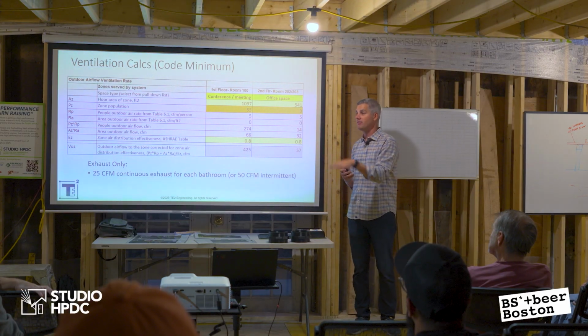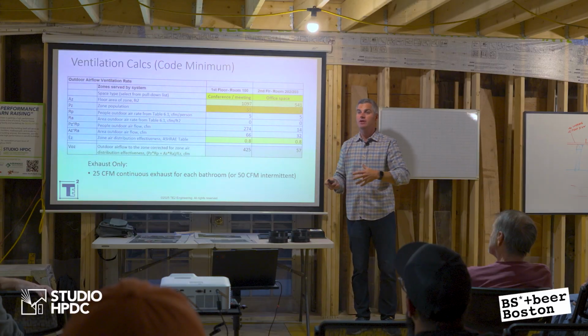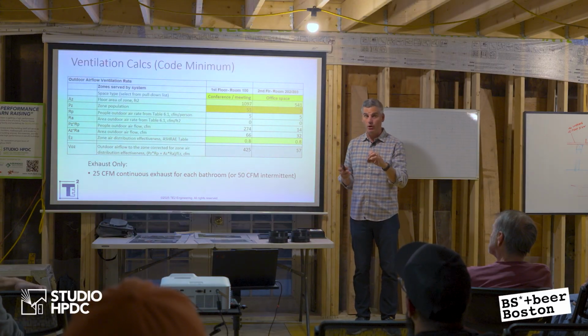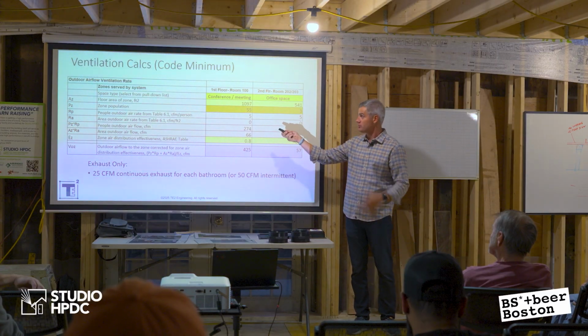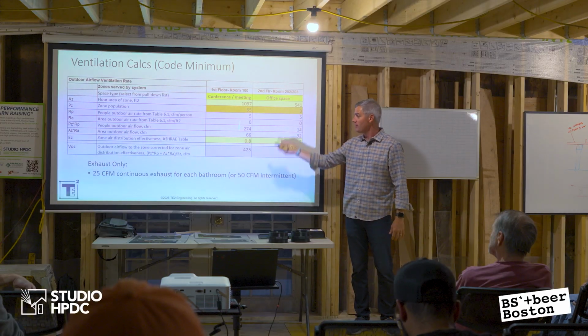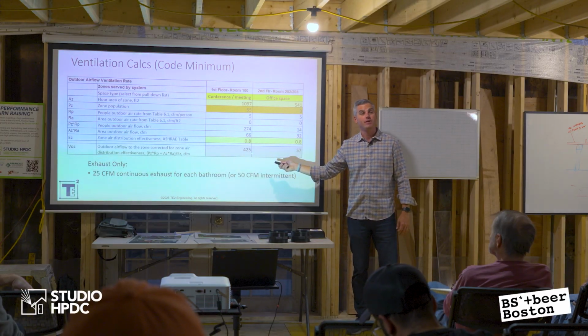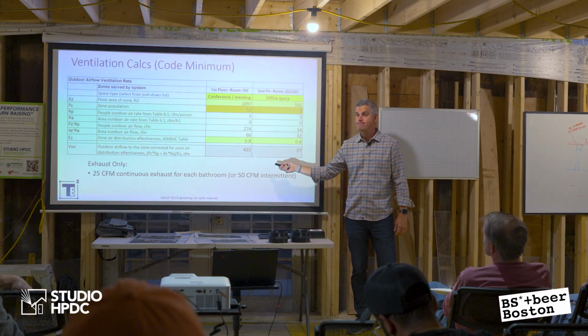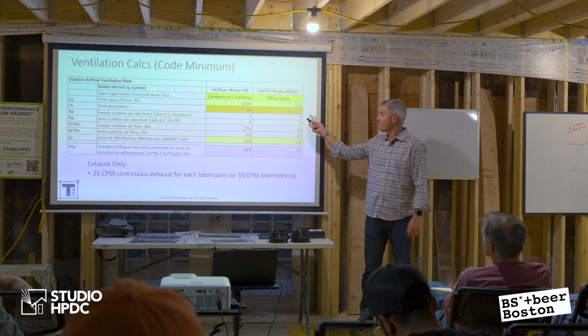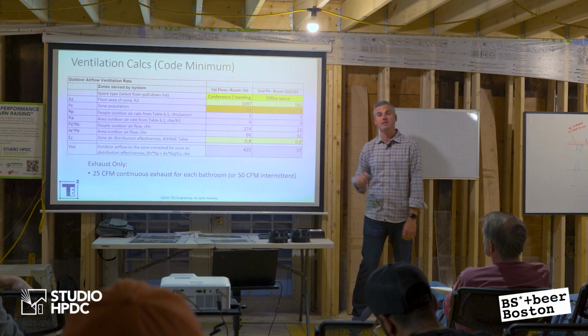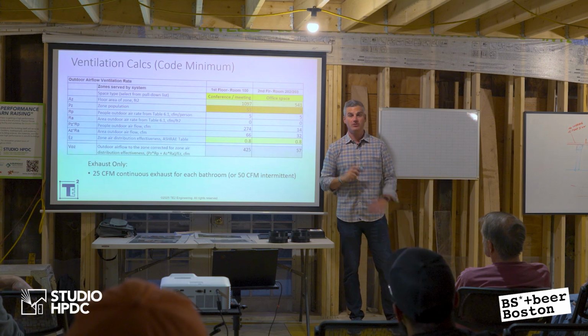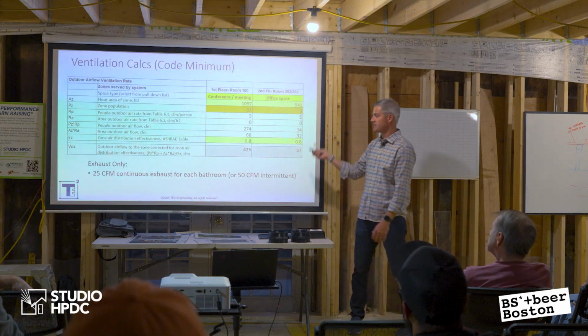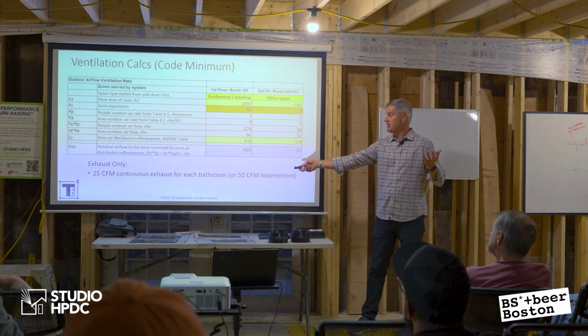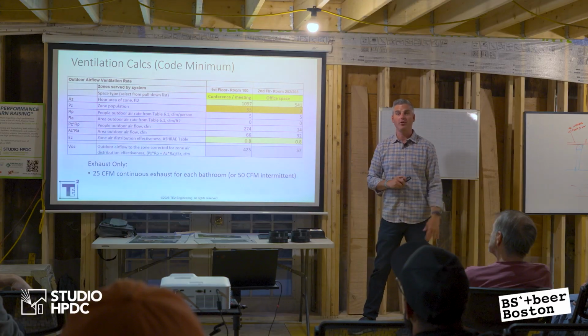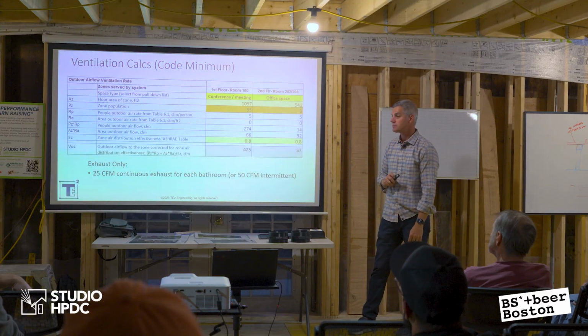What is this space going to be defined as? And that's a client conversation, and that's trying to understand what that means. But the load right now is based on this being a conference room, defined as a conference room, which means it's 55 people. Guess how much ventilation we need? 425 CFM. And upstairs is an office space, 541 square feet, 3 people, 57 CFM upstairs, based on the commercial code and these defines. We need 25 CFM continuous for each bathroom, or 50 CFM intermittent for the 2 bathrooms that are going to be over there.